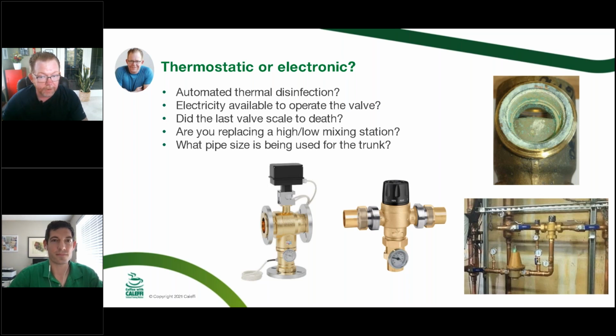The other thing to keep in mind is, did the last valve scale itself to death? Did you have a water quality issue? I was out with a really good plumber this morning who was telling me about a job where they've replaced the mixing valve more than once. And again, that's something to keep in mind, not just whether I'm doing thermostatic or electronic.